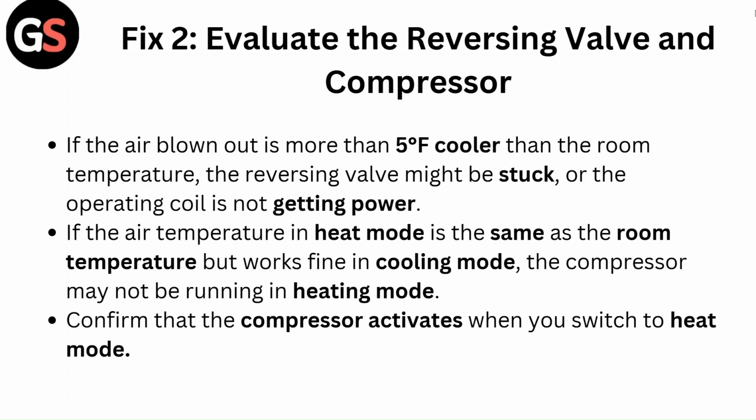Fix 2. Evaluate the reversing valve and compressor. If the air blown out is more than 5 Fahrenheit cooler than the room temperature, the reversing valve might be stuck or the operating coil is not getting power. If the air temperature in heat mode is the same as the room temperature but works fine in cooling mode, the compressor may not be running in heating mode. Confirm that the compressor activates when you switch to heat mode.